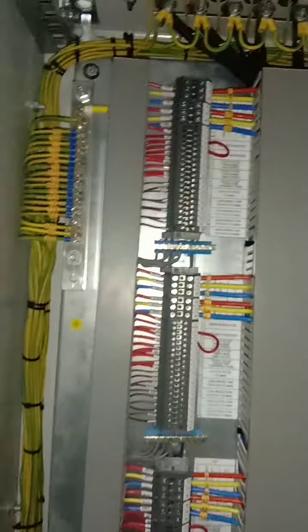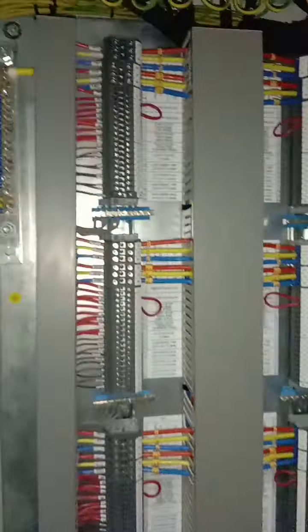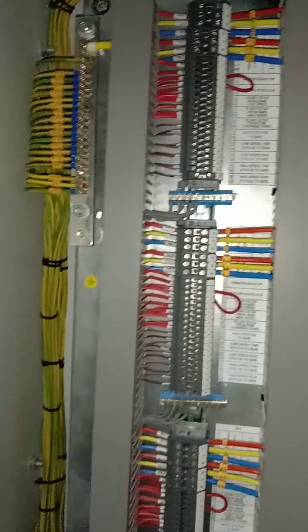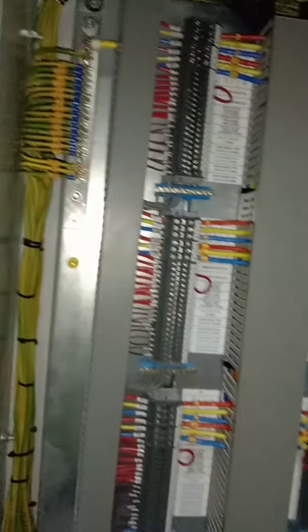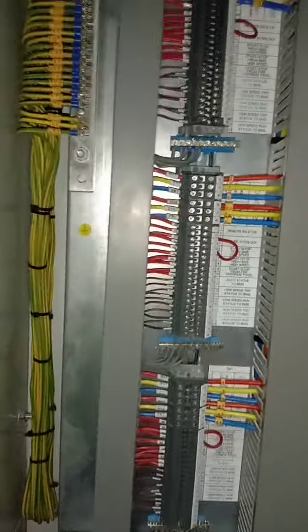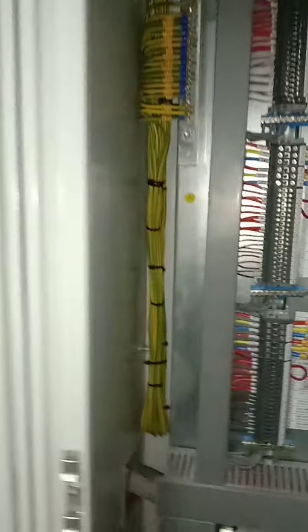Usually for the high speed, since it has a high capacity of power, the cross-sectional area of the cable is also usually high. So if you see a high cross-sectional area and a low cross-sectional area leaving from one particular motor, it means the high speed will have the highest cross-sectional area of the cable.